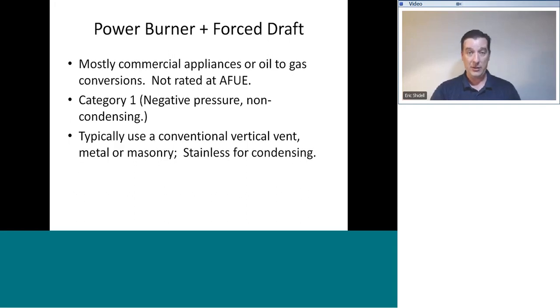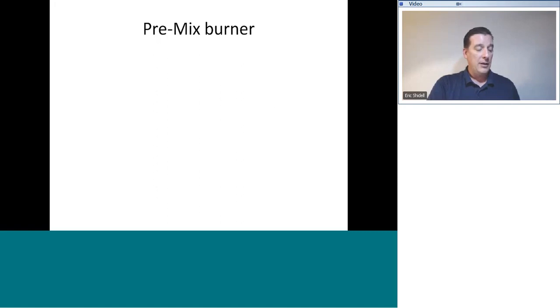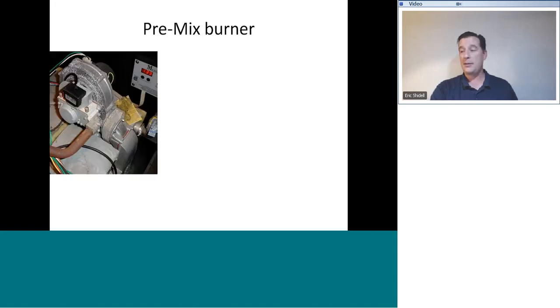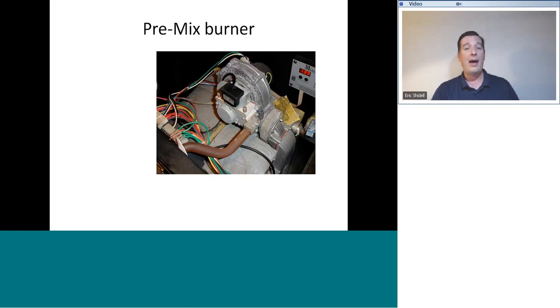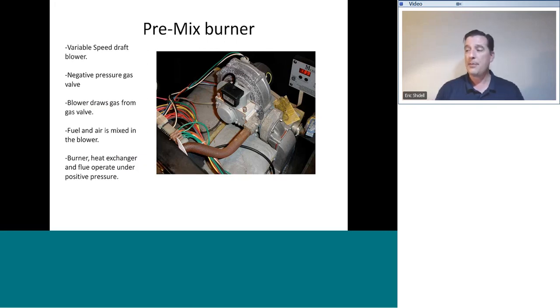The last burner we're going to talk about today is called premix burner. And these are becoming far more popular, especially in certain kinds of appliances. Here is a shot of half of a premix burner. You can't see the other half until you disassemble the whole thing. So we'll show you the top half first. Premix burners look an awful lot like a power forced draft burner, but they are not. They are very different. They have some similarities. First of all, there is a fan, there's a blower, and it blows into the inlet of the heat exchanger, just like the power burner did.